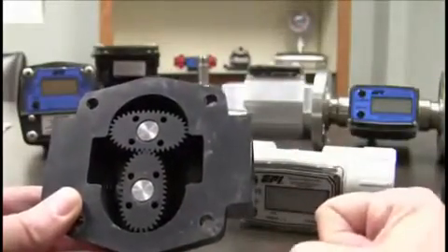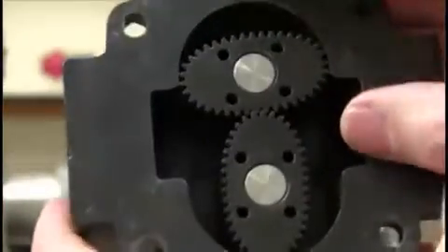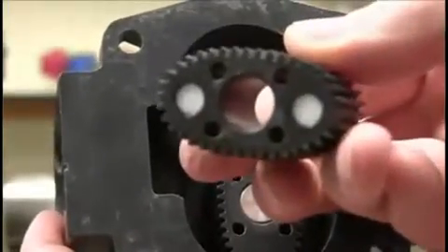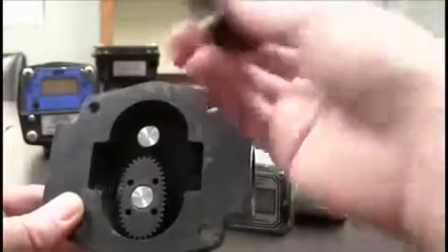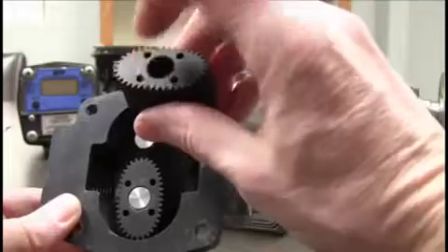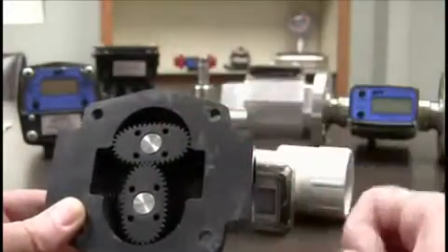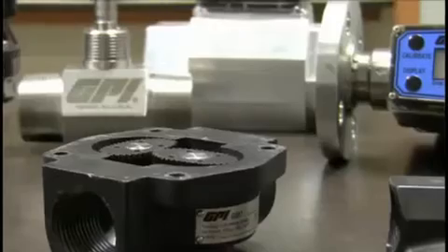Now it works the same way. You've got magnets on your rotors. Instead of the magnet being inside the display like here, you've got the magnets in the rotor. It actually goes through the bottom side here, and so the magnet's on this side. So when you have that in there, the magnet is sensed by a Hall effect or a reed switch. Here we've got the reed switch. As you can see underneath, you've got actually two reeds.